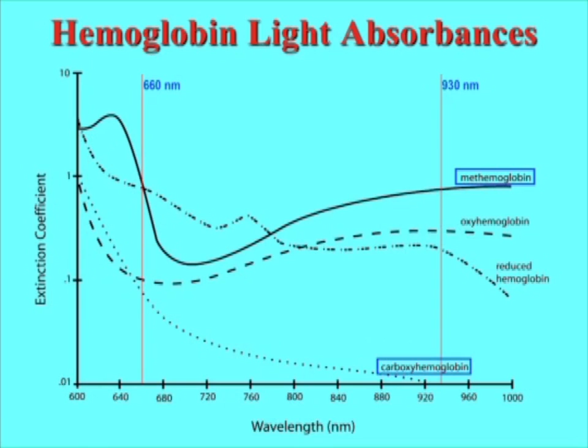What happens? Well, here is a landmark experiment. Look at the date on this. 1987, I took what was then the leading conventional two-wavelength pulse oximeter. This is done in dogs. We exposed the dogs to carbon monoxide, and by the way, we were only using about 100 parts per million, which is a very low level. That level is fatal to anyone if you were exposed long enough.